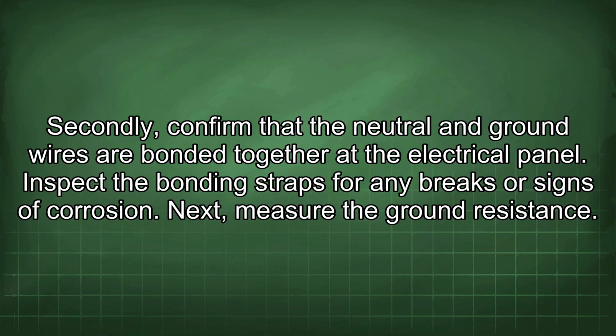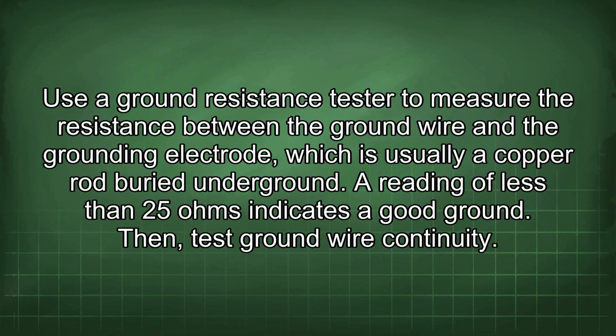Next, measure the ground resistance. Use a ground resistance tester to measure the resistance between the ground wire and the grounding electrode, which is usually a copper rod buried underground. A reading of less than 25 ohms indicates a good ground.